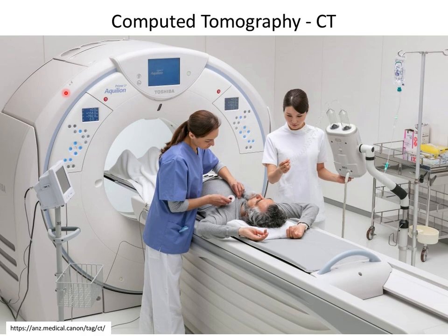The vendors just bit the bullet and said, okay, we're just going to keep making these detectors bigger and bigger. It's a lot of data to get out. This is a whole bunch of interesting engineering problems to solve to make that happen. This is a Toshiba scanner. It actually has 320 detectors in Z and about 1,000 in the other direction. So this guy's getting hooked up to an EKG monitor. This is an injector, so you're going to inject X-ray contrast into the patient and then dynamically image after that injection has occurred, so you can see the contrast between the vessels and the background.